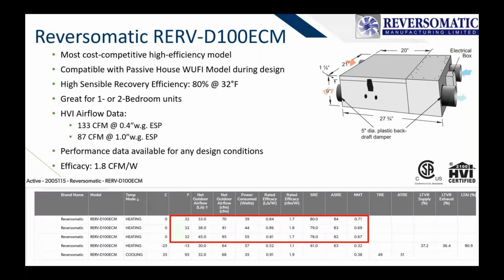So this is a very high efficacy. And down below, I actually highlighted the HVI data, where there are 3 design points at 70 CFM, 81 CFM, and 95 CFM, where it only decreases by 1% SRE per data point. So, pretty good SRE for the airflow that you get here. Definitely worth designing around from the front end and could be a good substitution as long as the efficacy works.